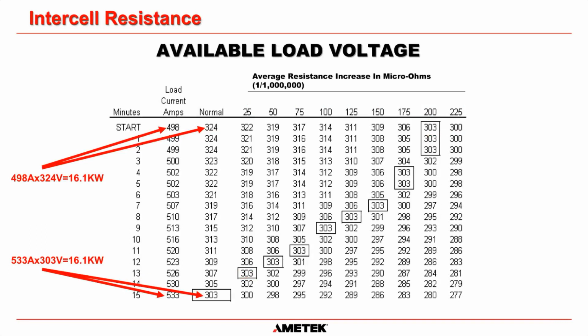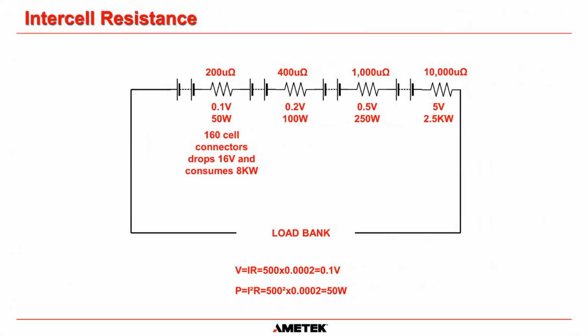It's kind of difficult to understand from the table. So what I've done is I created this diagram, hopefully that will show you a little bit better. So in this one here, we've got 1, 2, 3, 4 batteries connected in series. And these resistances here are symbolizing the intercell connection resistance between one battery's negative post to one battery's positive post. Okay. And then we have our load bank connected here, which is going to be discharging the batteries at that 500 amp level that we mentioned in the last slide.